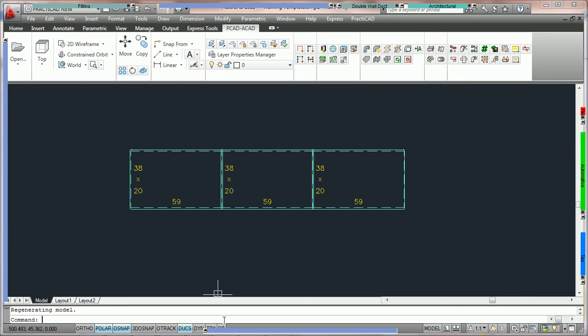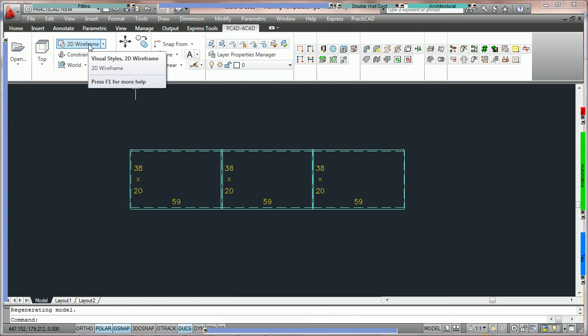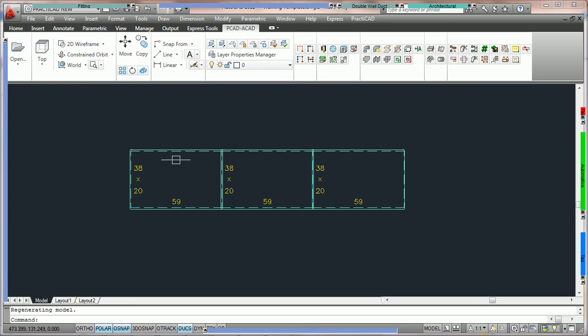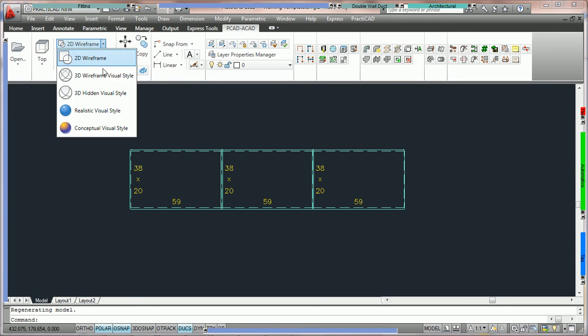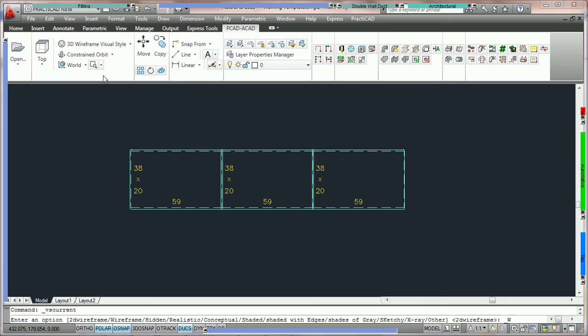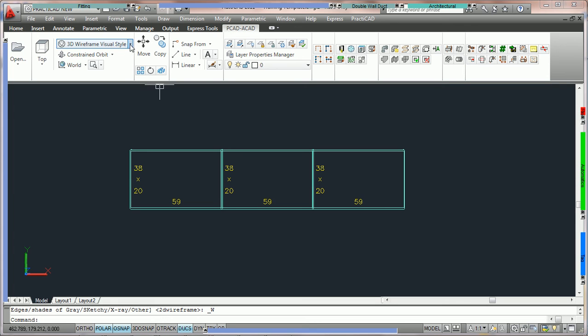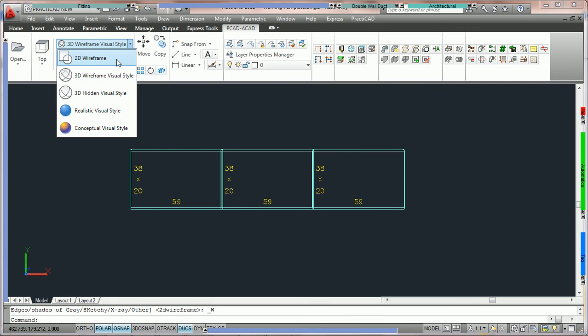The last thing is the most common reason why your liner wouldn't be dashed. If you have not chosen the proper AutoCAD visual style, you're not going to see your liner. Only the 2D wireframe visual style is going to represent these lines correctly. That is one of the reasons, once again, we always plot in 2D wireframe. What we're going to do here is switch it to 3D wireframe for a minute and now you can see that the liner is one solid continuous line which is not what we want. So you must make sure that you keep it in 2D wireframe.